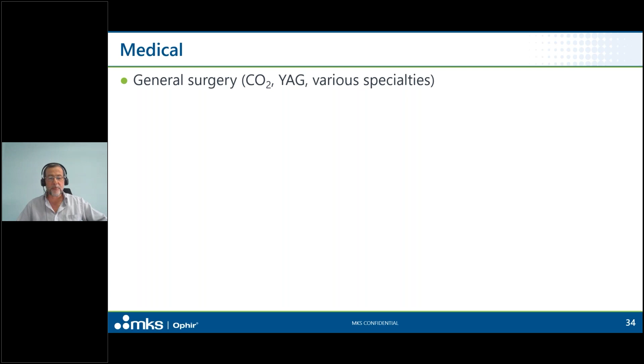So when one thinks of laser-based medical applications, probably surgery is one of the first that comes up. General surgery, slicing, dicing. Typically, those kinds of applications use either YAG lasers or CO2. CO2 is still a very popular laser of choice in surgical applications where the target tissue is very close to important non-target tissue, including, for example, many laparoscopic procedures and gynecological applications. It has a very shallow absorption depth, meaning CO2 10.6 micron wavelength light is very readily absorbed by water, and we are, to a very large degree, water. That makes it easy to be highly specific in what tissue I'm zapping and what tissue I'm not zapping, so I can minimize the thermal risk to nearby tissues.